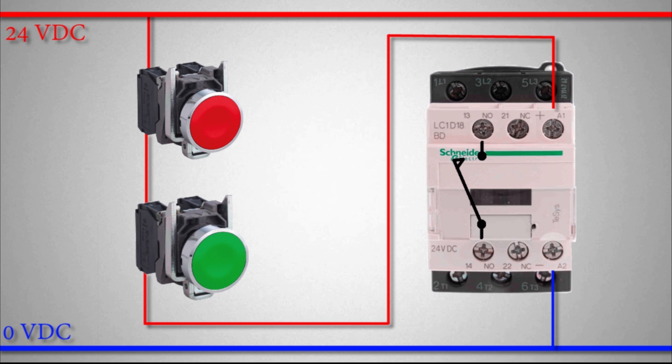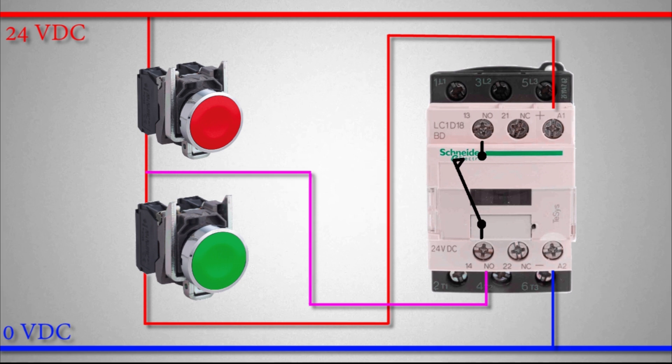In the next step we will modify the wiring so that if the green normal open push button is pressed once, the contactor keeps turned on even after we release the green push button. For this, we connect a wire from the output of the NC contact of the green push button to the normal open auxiliary contact of the contactor, and from the other end of that auxiliary contact to the A1 terminal.